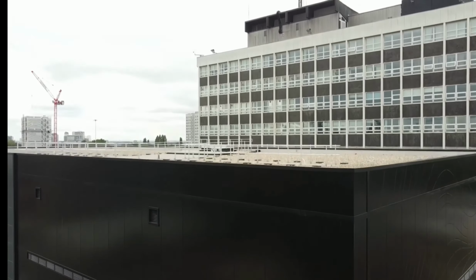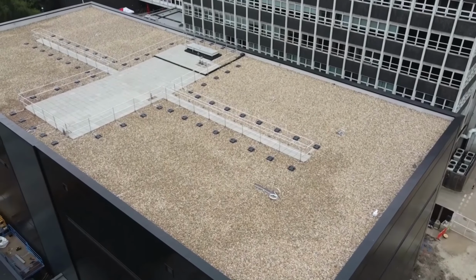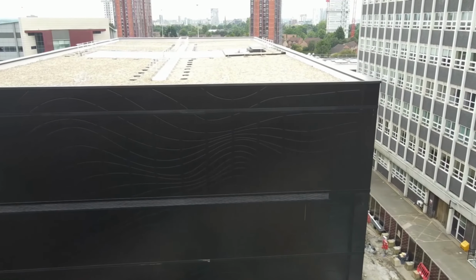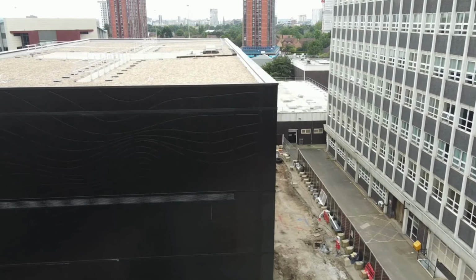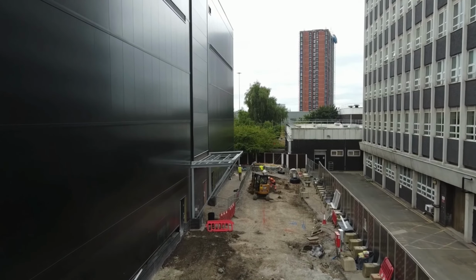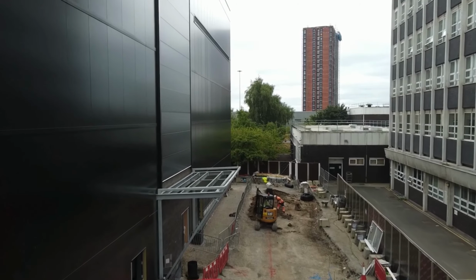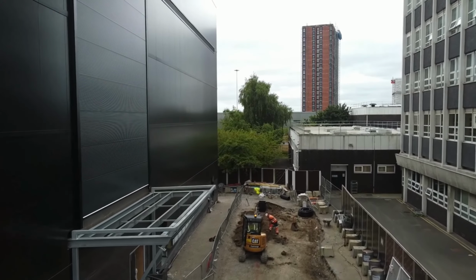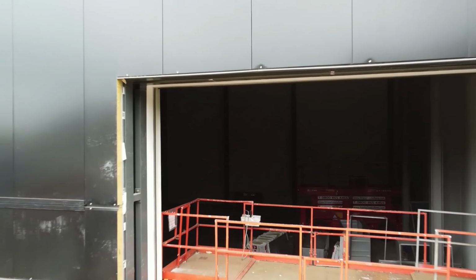So where we're at the moment is the building's done. The inside of the building is more or less done, and what they're putting in now is a HVAC. So the HVAC is just £6 million alone, just for the cooling equipment and the heating equipment to keep that chamber either hot or cold. And it keeps it hot or cold to 0.5 of a degree. So if you speak to anyone about environmental chambers in the dairy sector or meat products, it's unheard of that such a large chamber is conditioned to that extent. But it gives us this test bed where we can look at whatever we want, when we want. It can be whatever measure temperature is outside, and we can change it inside.